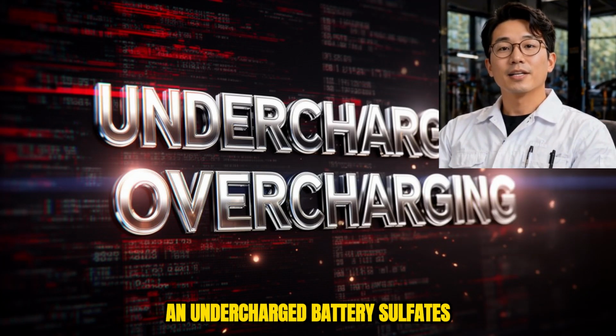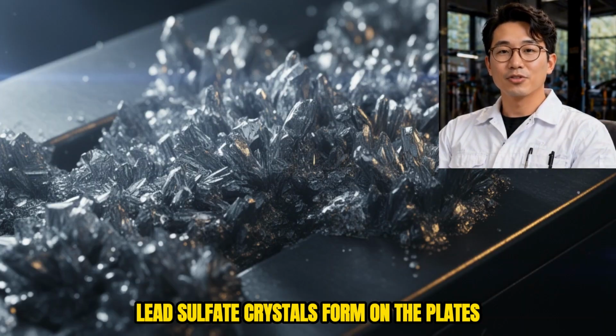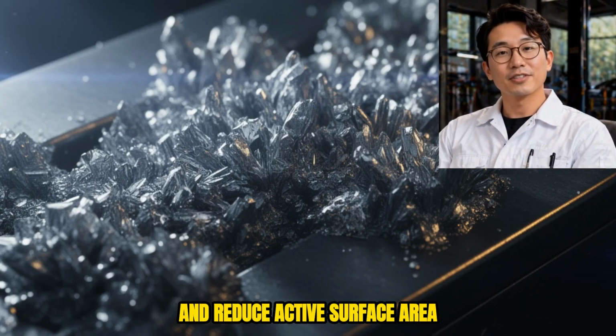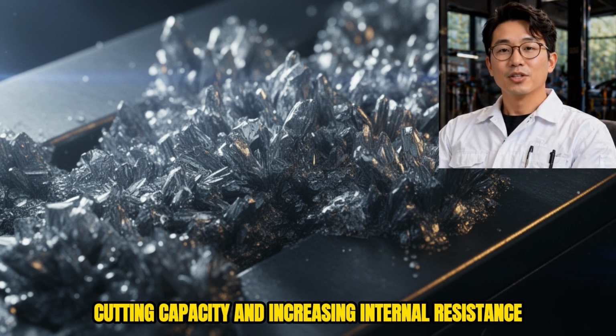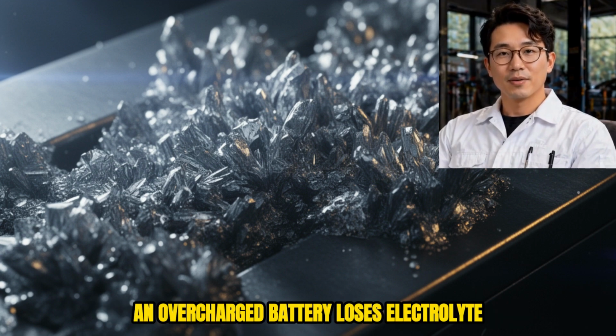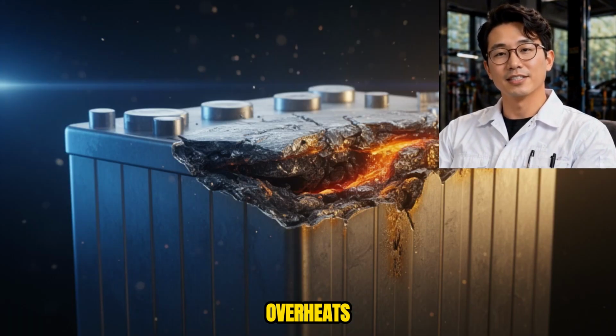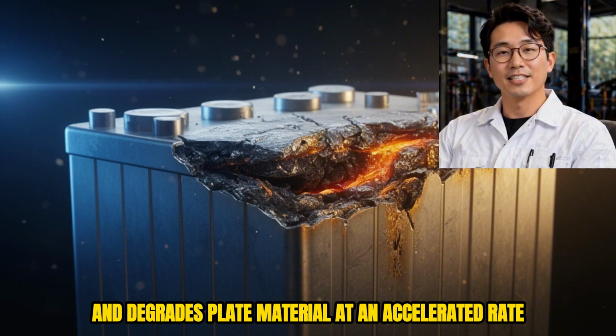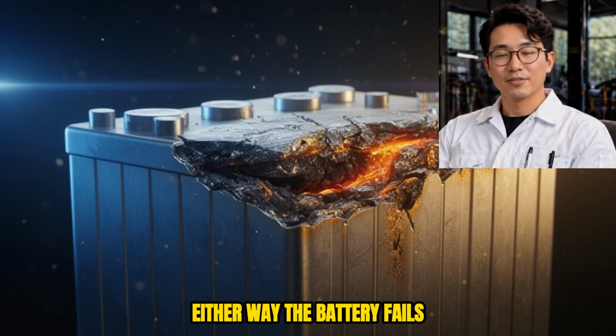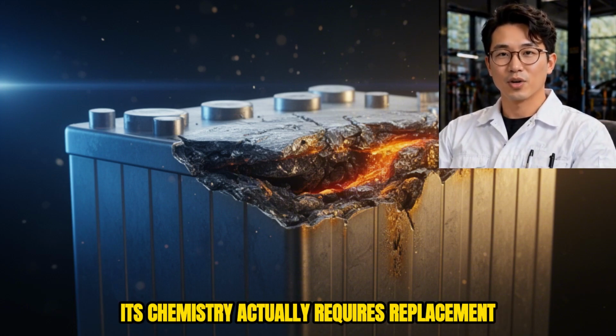An undercharged battery sulfates. Lead sulfate crystals form on the plates and reduce active surface area, cutting capacity and increasing internal resistance. An overcharged battery loses electrolyte, overheats, and degrades plate material at an accelerated rate. Either way, the battery fails years before its chemistry actually requires replacement.